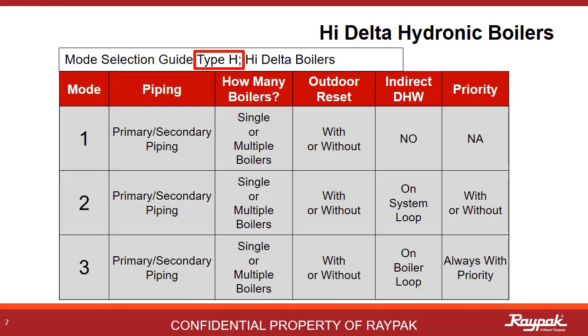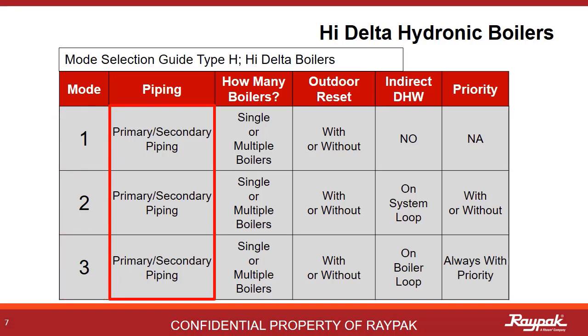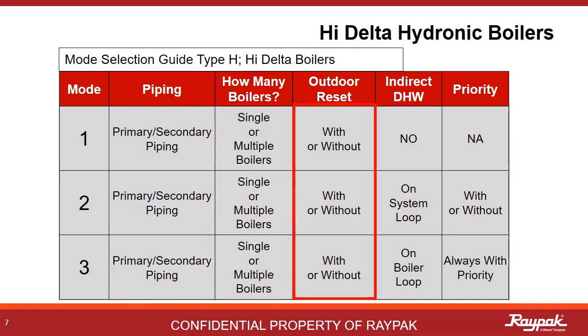This is a summary table for the hydronic-type boilers. There are three modes to choose from: Mode 1, 2, and 3. All must be plumbed primary-secondary, as the high-delta boilers are low-mass. All three modes can be applied to single or multiple boilers, and all can run with or without outdoor reset. The difference lies in the presence or absence of an indirect hot water system. If there is no indirect, then it is Mode 1 — this is the most common configuration.